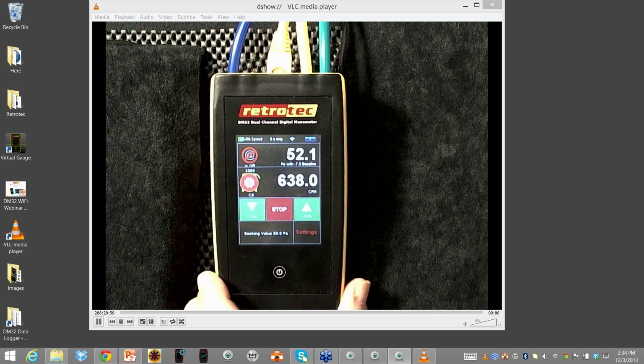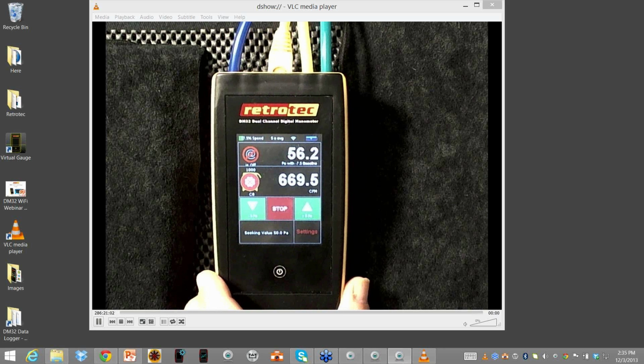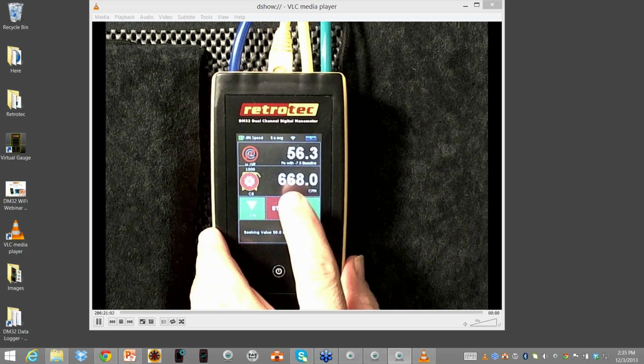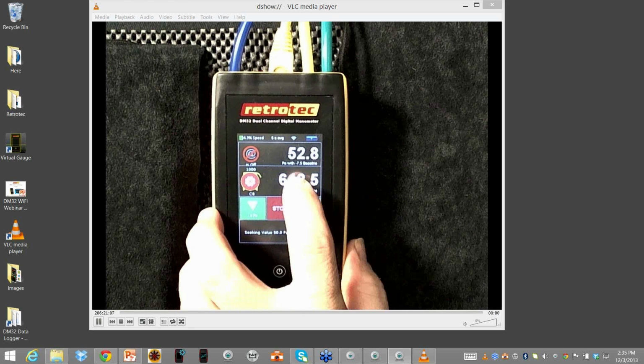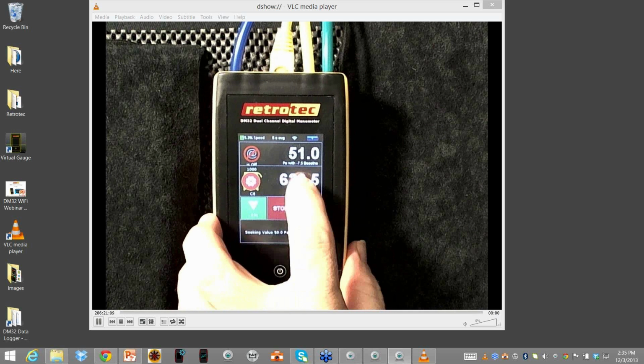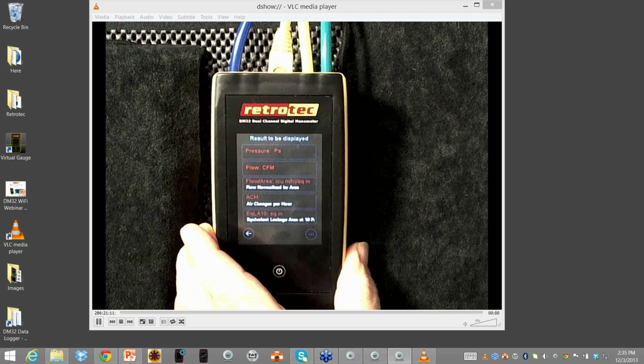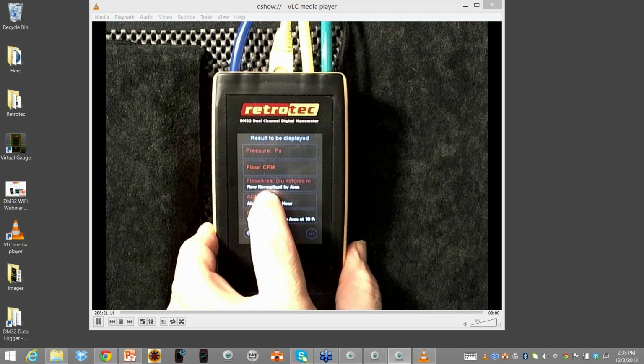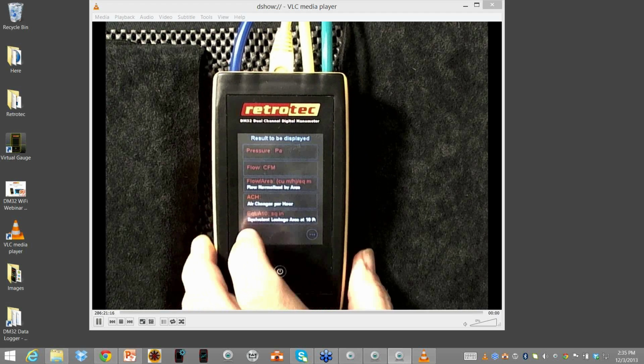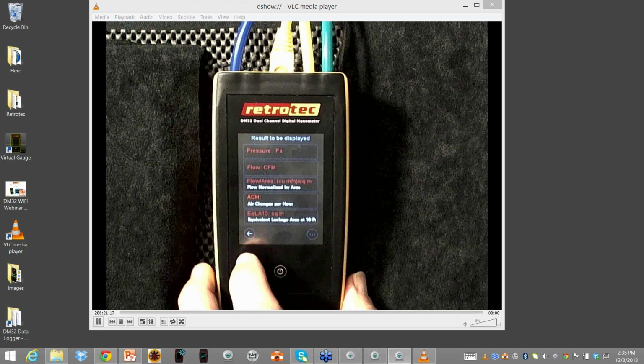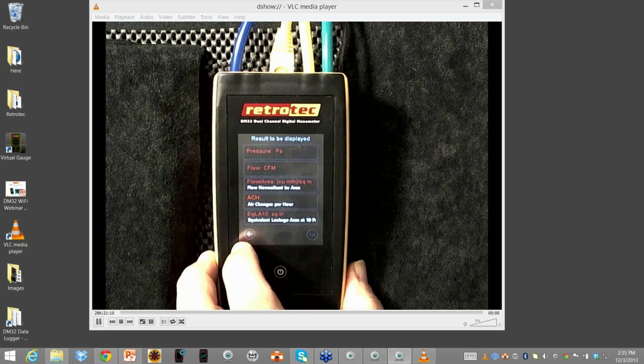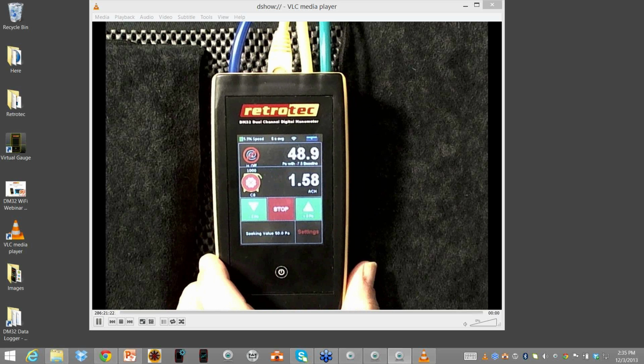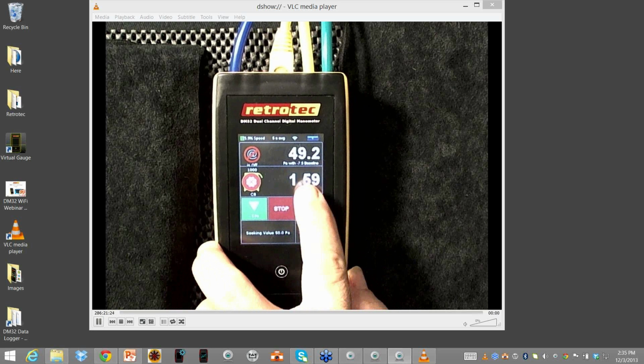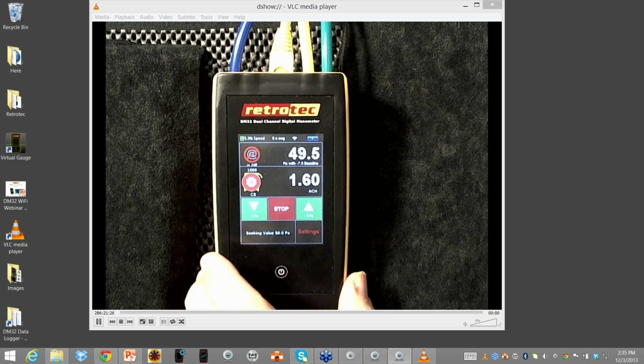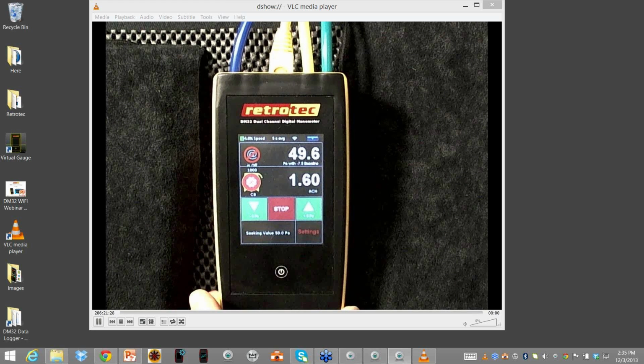Most people may be used to working with CFM, pulling their calculator out to determine what I have. But what I can do now is go into my settings and say I want air changes per hour, calculated on the volume I've already entered. I go back, and now I have air changes per hour showing up right here automatically as the gauge goes live.